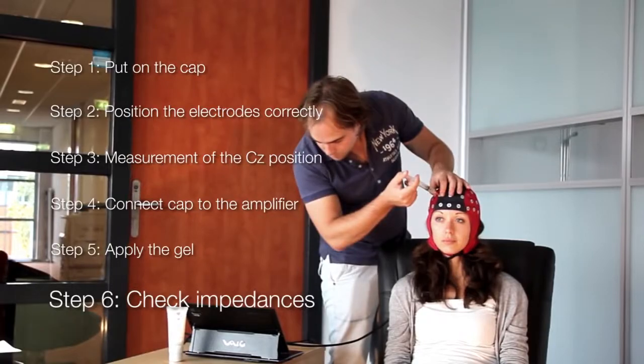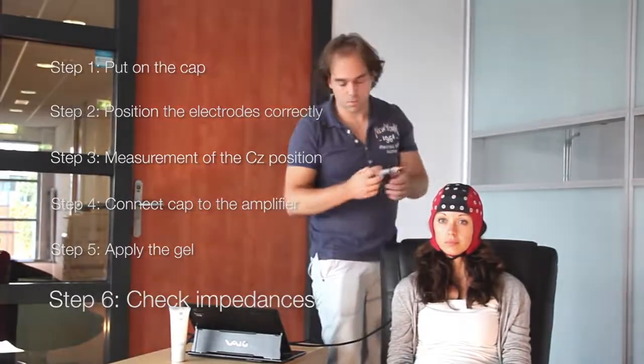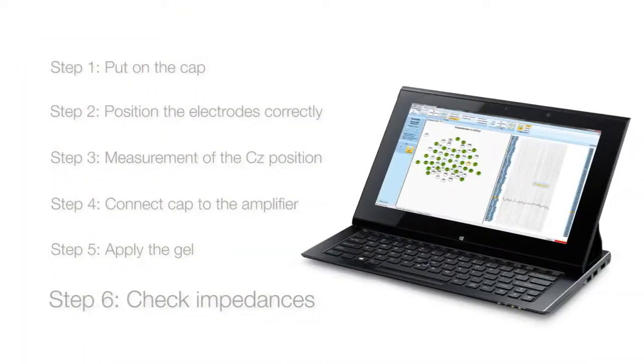Verify that there isn't too much drift or noise on any of the channels as these may be symptoms of high impedance. Acceptable electrode impedance levels are dependent upon the quality of your EEG amplifier.